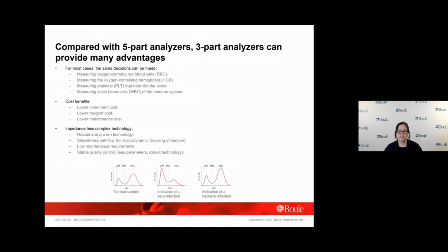Beyond this, a 3-part instrument can provide cost benefits in that these instruments are often cheaper and require fewer reagents. A 3-part instrument is also based on robust and well-proven impedance technology. These instruments typically require less maintenance, and as they only use impedance, these instruments are generally less complex, which is also reflected in the quality control with fewer parameters to monitor.